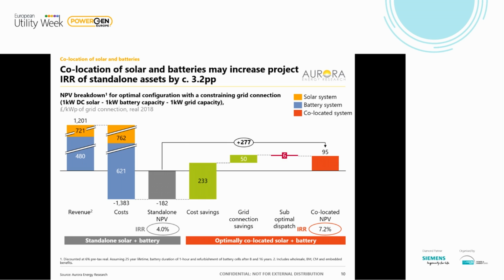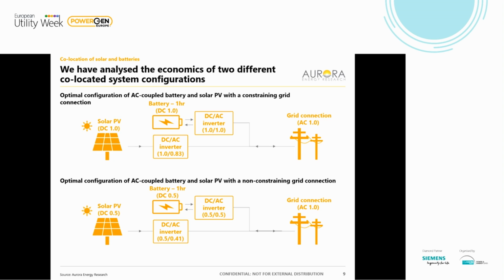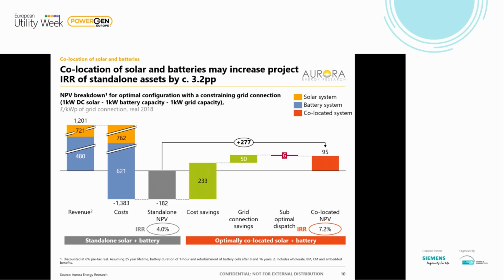Now, what happens if you co-locate is, firstly, you realize a big cost saving, coming from three points: you save on the balance of system, on fixed costs, and on the grid connection. You have the grid connection saving because you've oversized, so you have a smaller grid connection, and you have a suboptimal dispatch impact.